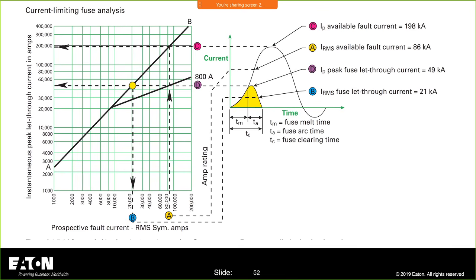Now, if it's a circuit breaker, I can't do that because a circuit breaker is going to be introducing what they call dynamic impedance. It's going to try to open the circuit, which is going to reduce the short circuit current peaks and whatnot. And now I get into a beast that is not clear cut. That is how we use the up, over, and down method, and that's how I use this table or this chart. I use this chart to determine the peak and determine my let through when I'm trying to determine whether or not I'm going to protect a piece of equipment that is static.